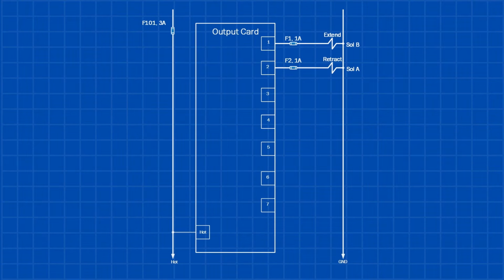Since we have system pressure, it's almost always an electrical issue, about 99% of the time. The problem is usually either a blown fuse on the incoming side of the PLC output card or a faulty output card itself. Start by checking the fuse. If it's blown, replace it and run the cycle again. If the fuse blows again, that's a clear sign the PLC output card is bad, and you'll need to replace the card.